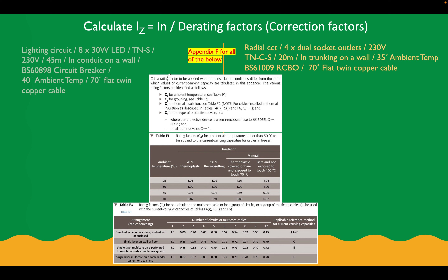C is a rating factor to be applied where the installation conditions differ from those for which values of current carrying capacity are tabulated in this appendix. In simple terms, the current carrying capacity tables inside the on-site guide or BS 7671 are based on cables tested at certain conditions. If the ambient temperature is larger, if they're grouped, if it's in insulation, or if it's a different type of fuse, this all affects the current carrying capacity of the cable.